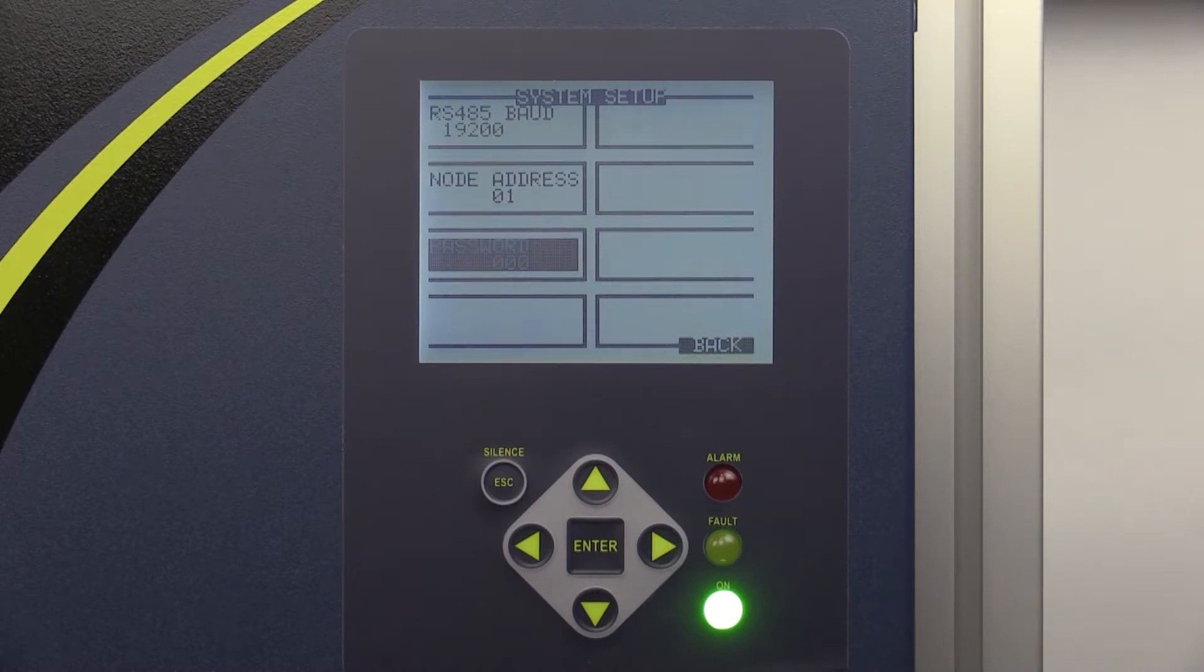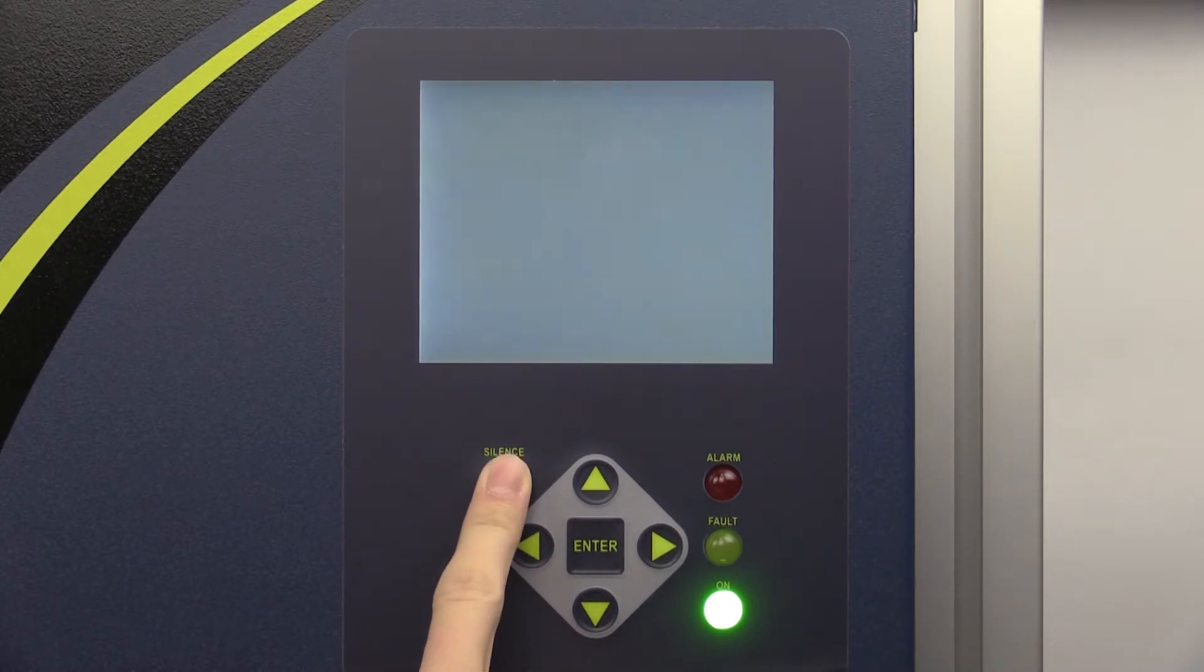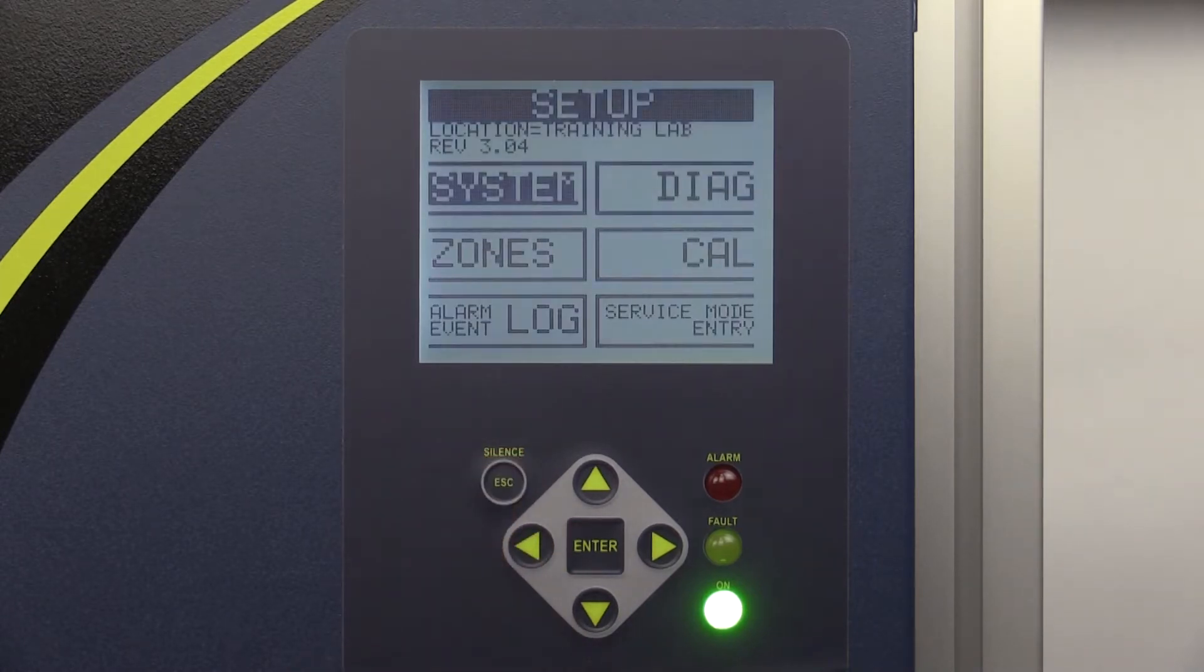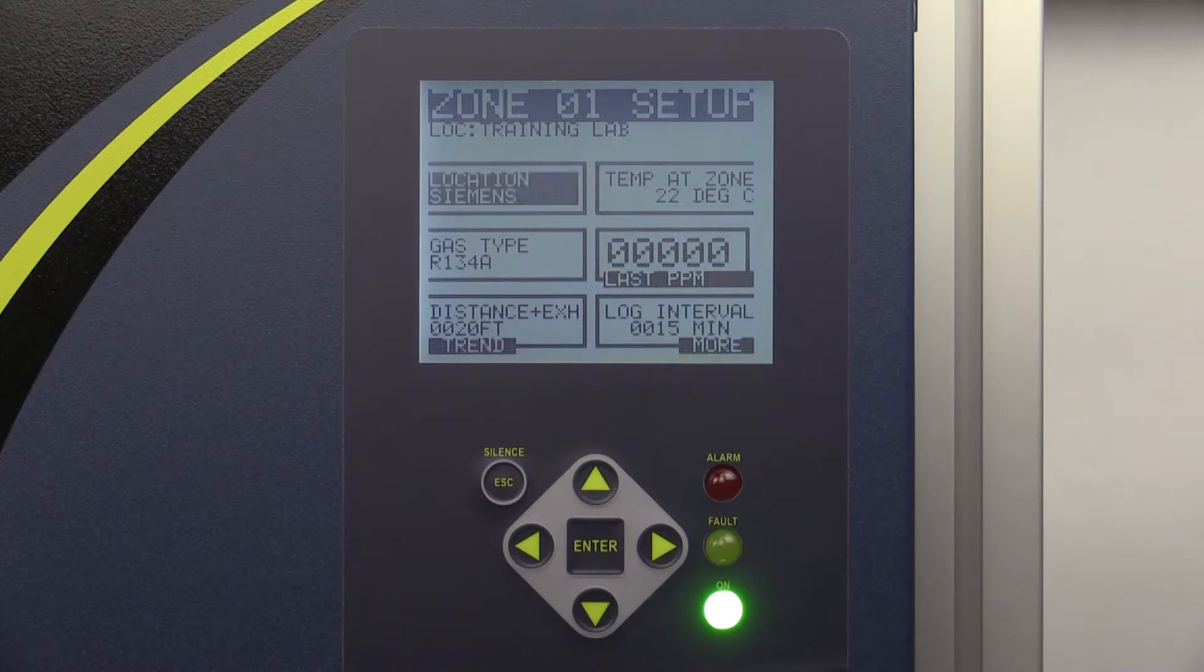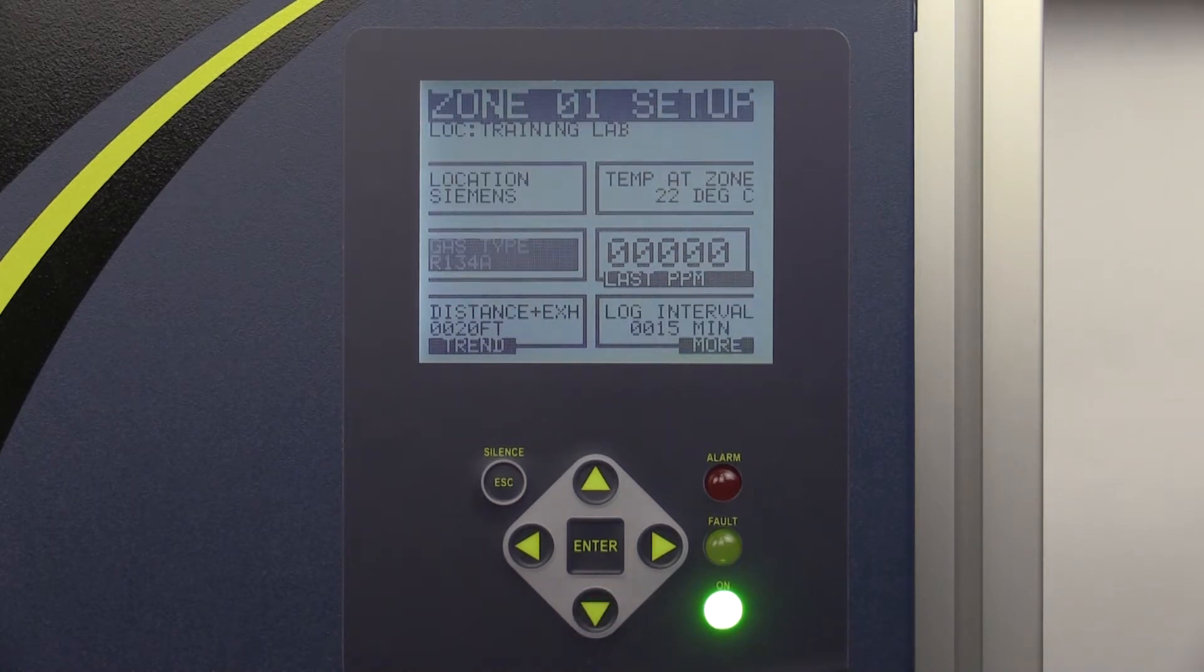Press the Escape button on the keypad to return to Setup screen. Enter the Zone Setup screen by highlighting the Zone tabs on the Setup screen and pressing Enter. The screen should now read Zone 1 Setup. Edit the Location tab to name the location of the specified zone. The Gas Type tab determines what gas the system will detect at a specified zone. Change the tab to the desired gas. Each zone is capable of searching for a different gas.